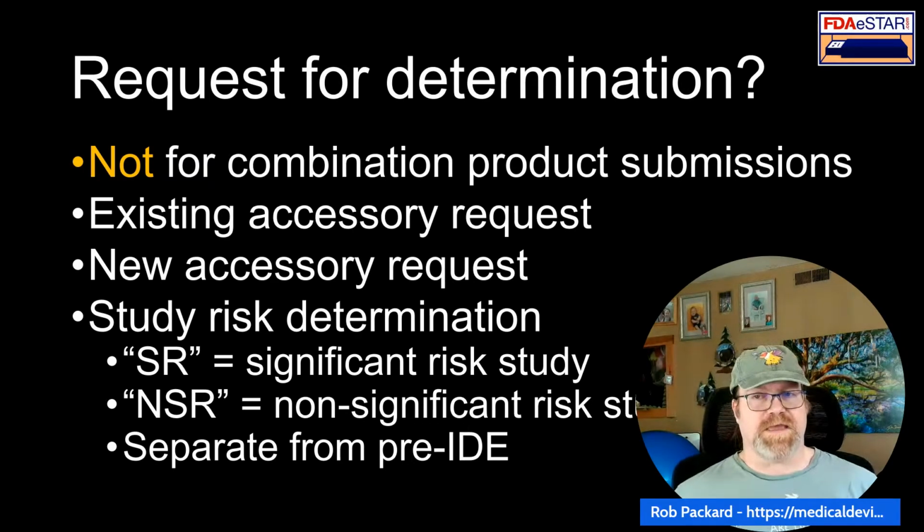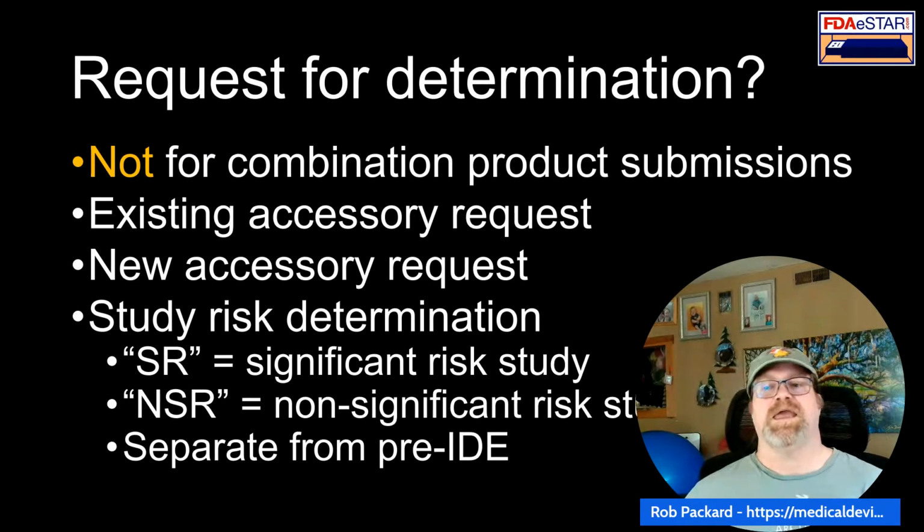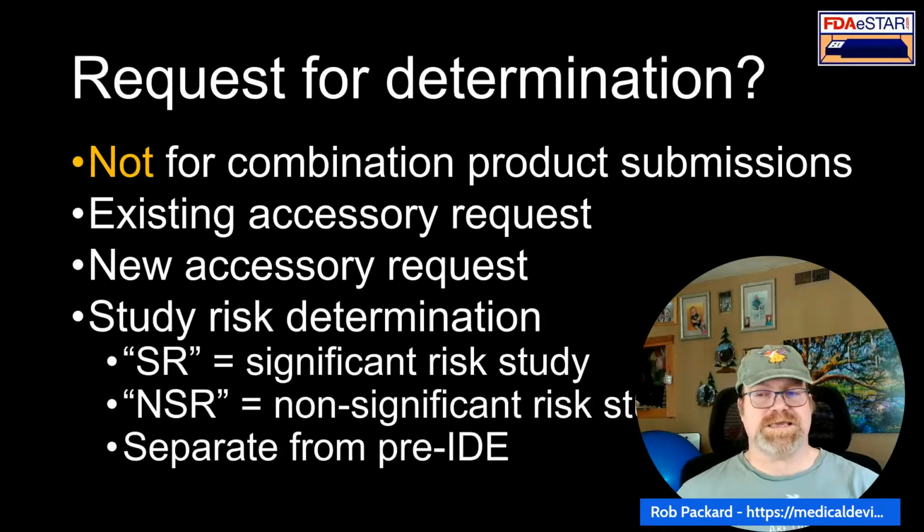But the study risk determination: if you're not absolutely sure that it's an NSR study, you're probably going to do a study risk determination, submit it to the FDA, and now you can use the PreSTAR for that. And you would do that separately from your pre-IDE meeting. You'd be asking for feedback on a protocol, so you're not sure that the protocol is final yet. You submit your IDE when your protocol is final and all your safety testing is done except for the clinical study.